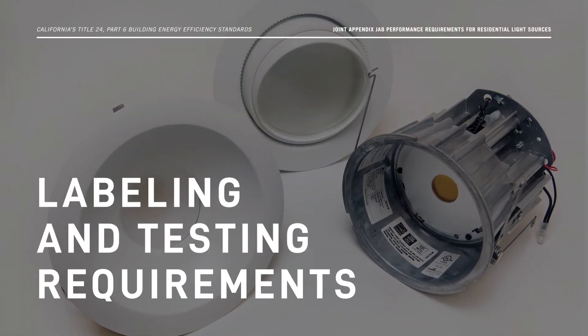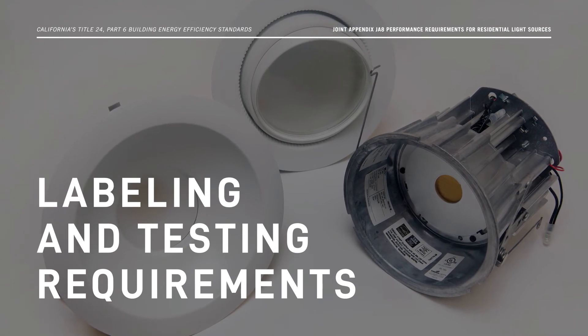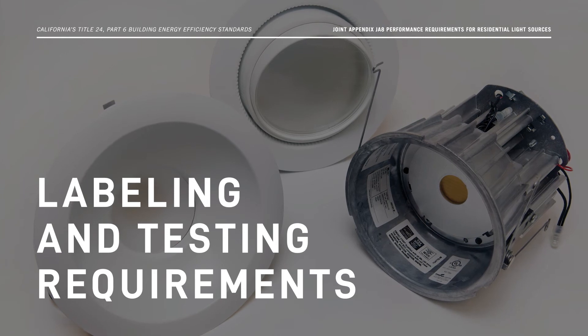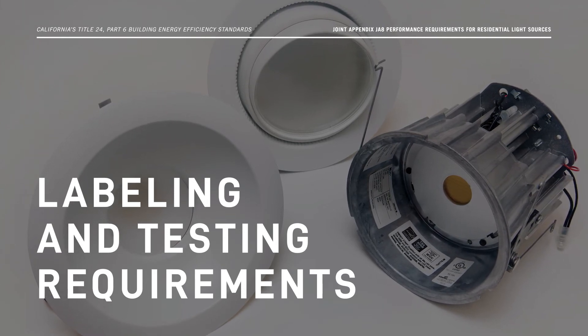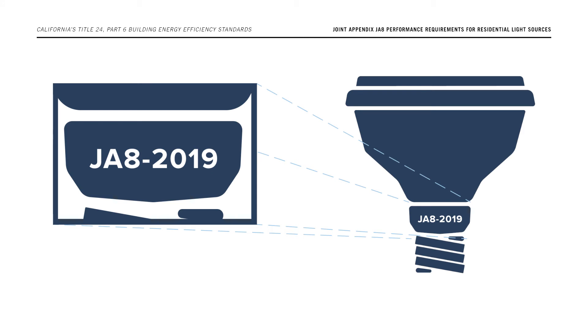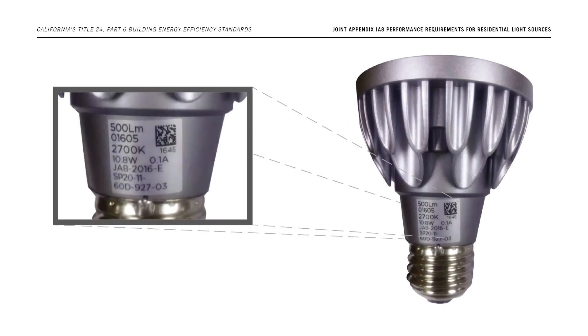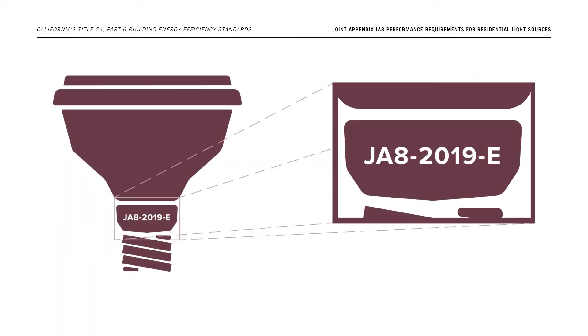In addition to these performance requirements, JA8 compliant products must also adhere to labeling requirements to help enforcement agencies, contractors, and consumers easily identify high-efficacy products. For light sources to qualify as high-efficacy under JA8, they must include either a JA8-2019 or JA8-2019E marking on the lamp or luminaire. Lamps or luminaires marked with JA8-2016 or JA8-2016E are also acceptable. Light sources marked with JA8-2019E have passed the elevated temperature life test, indicating they may be installed in elevated temperature applications such as enclosed and recessed fixtures.